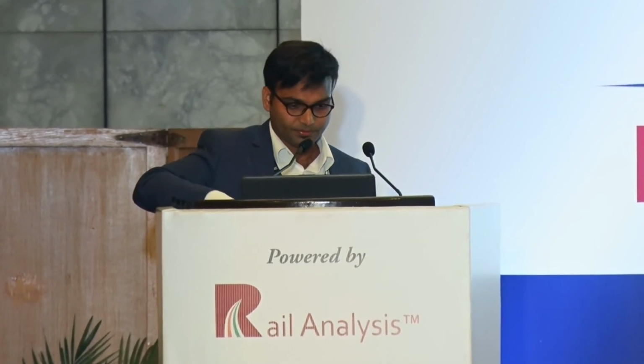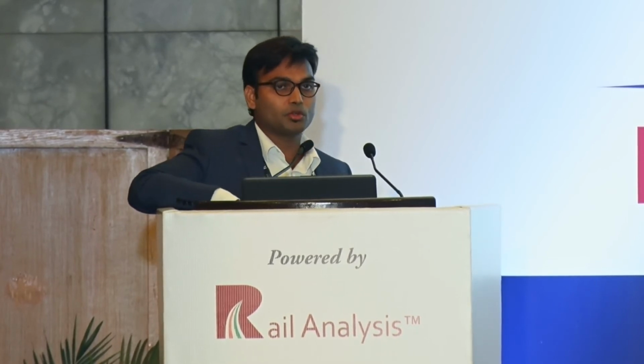And since it is a manual process, there is always a safety hazard. The staff may get electrocuted in case of not taking proper precautions. And in this case the maintenance time is also high. And if during the breakdown, this can directly affect the revenue operation. In Kanpur Metro, instead of using this portable short circuiting device, we are using automatic short circuiting earthing device. Again, we are using this first time in India.